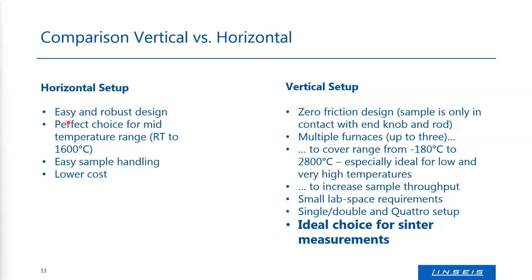In horizontal systems, samples are placed in a sample carrier — a half tube. When the sample is placed inside and moves, there is friction against the sample holder, which is not the case in a vertical setup. Therefore, it is better to use a vertical system for sintering measurements.